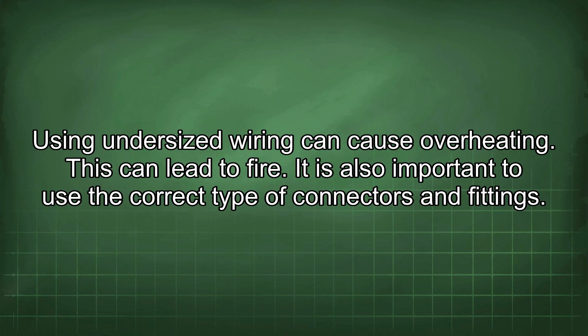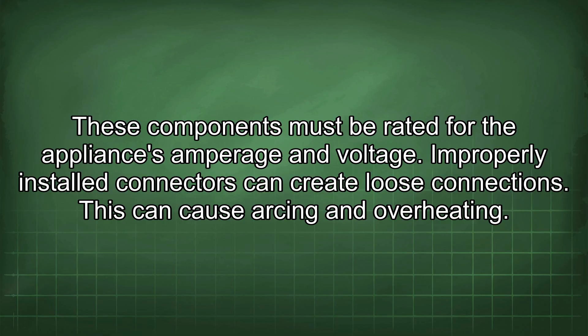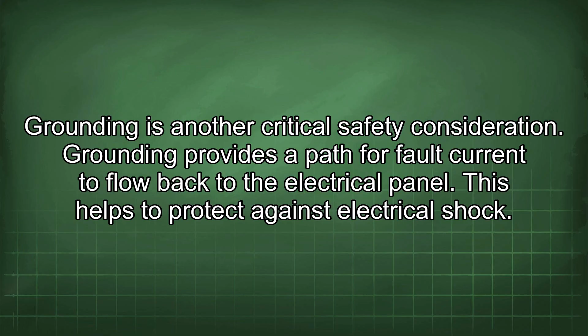It is also important to use the correct type of connectors and fittings. These components must be rated for the appliance's amperage and voltage. Improperly installed connectors can create loose connections. This can cause arcing and overheating. Grounding is another critical safety consideration. Grounding provides a path for fault current to flow back to the electrical panel. This helps to protect against electrical shock. The appliance must be properly grounded.